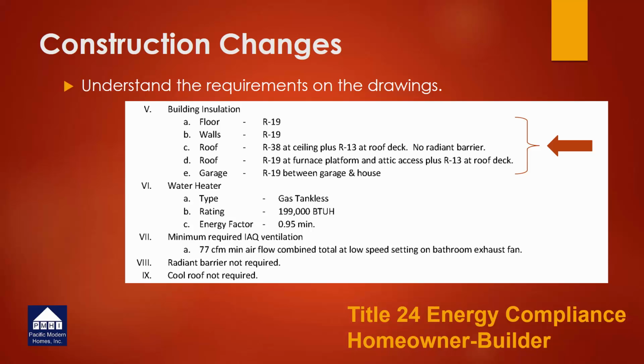We'll provide you with a water heater. We'll tell you, okay, it's going to be a tankless water heater or a tank water heater or a heat pump water heater, what the rating is for that specific unit that we included in the calculations, and the energy factor that it must comply with. We'll also provide you with information on the indoor air quality ventilation fan that must be installed under the new Title 24 requirements. In this case, they needed to have a fan or group of fans that could provide 77 CFM minimum airflow at the low speed setting on the fan.